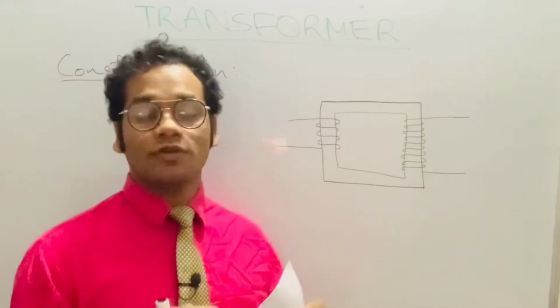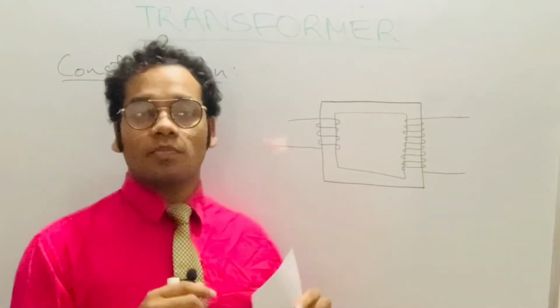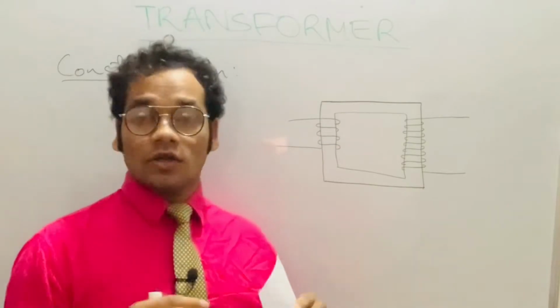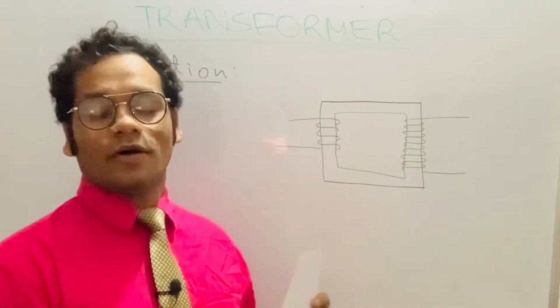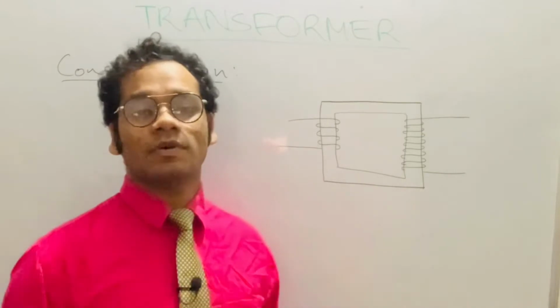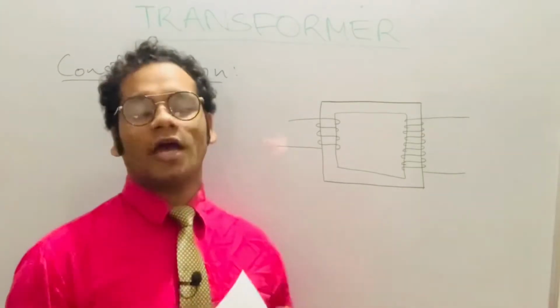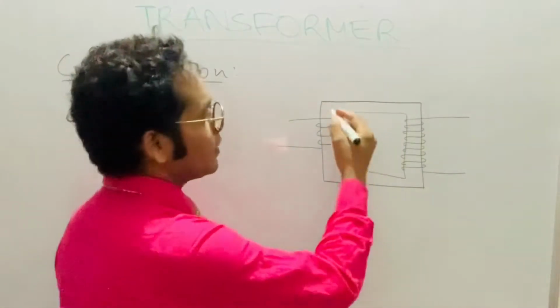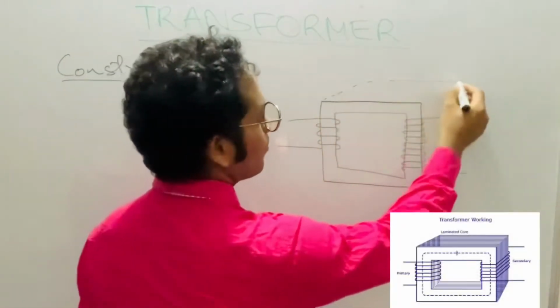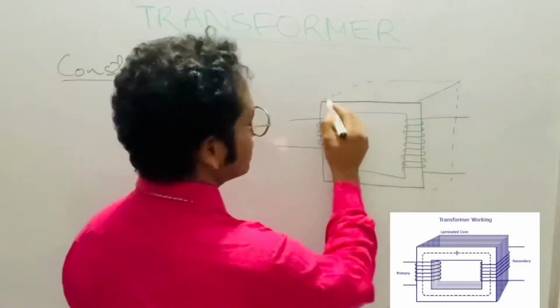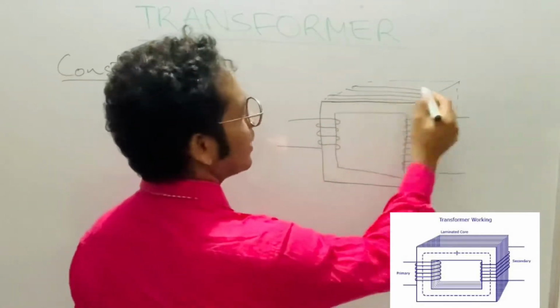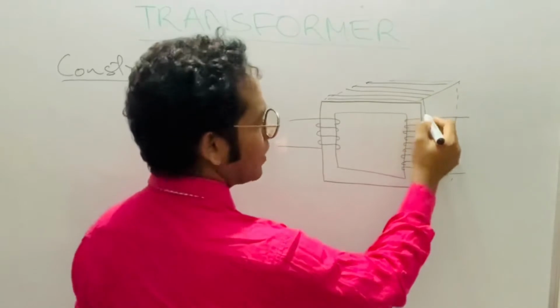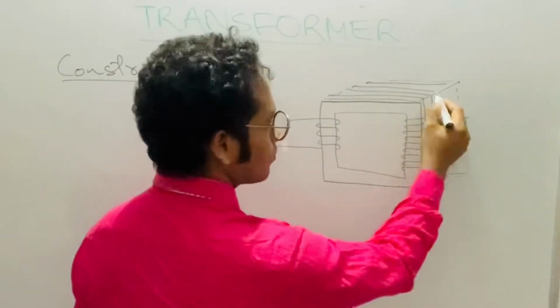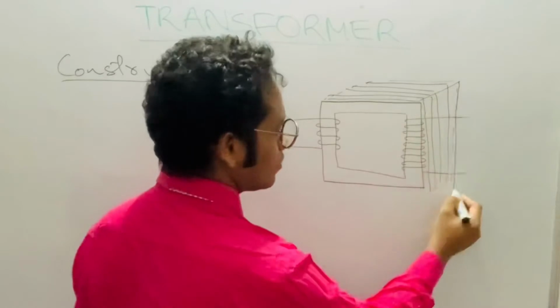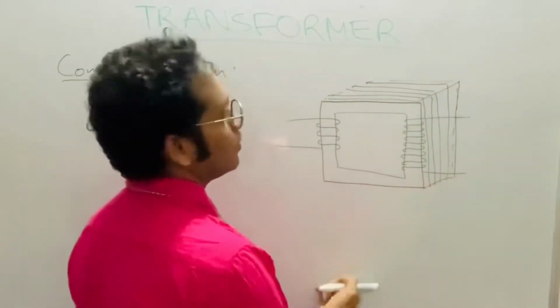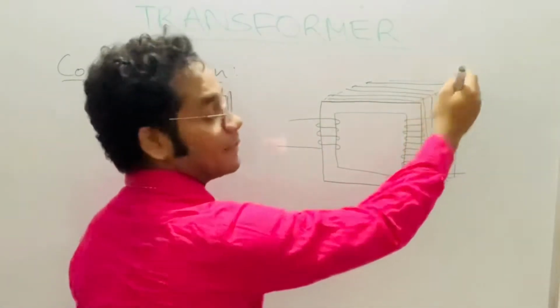As for the thickness of this lamination, it can be 0.30 or 0.35 mm. For a 50 Hz transformer, the thickness of one stamping or lamination can be 0.35 mm. So the core will have a number of laminations like this - I am drawing lines to represent the number of laminations. So all these are the laminations.